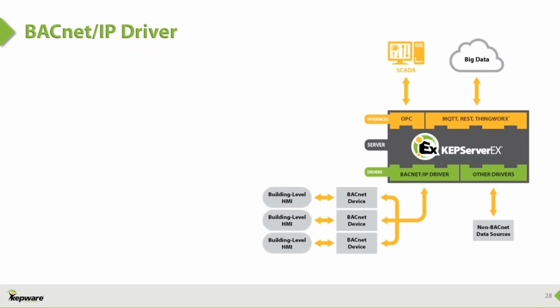While KEPServer might not be the first or obvious choice for many building applications—since there are many capable BACnet-specific SCADA systems on the market, including operator workstations that attach gracefully to SCADA or HMI systems—there are plenty of use cases where KEPServer combined with the BACnet driver makes a lot of sense. For example, you might want to link non-BACnet devices within your existing BACnet system. Perhaps you have non-BACnet PLCs controlling existing air handling and lighting equipment, but want to feed that information to your BACnet SCADA, or even trigger an action on the PLC based on BACnet events.